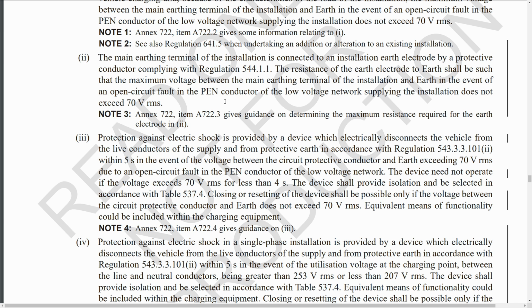Again, some rewriting has been done here, but nothing of any particular relevance. Now this is valid, but unfortunately to get this in any kind of useful option, the resistance of that earth electrode has to be incredibly low, and it says there in note 3, then you can actually have a look in the annex there, and it will tell you how you can calculate that.